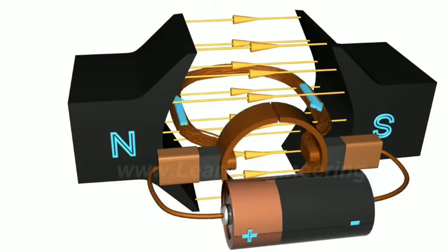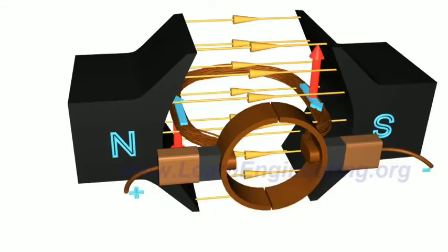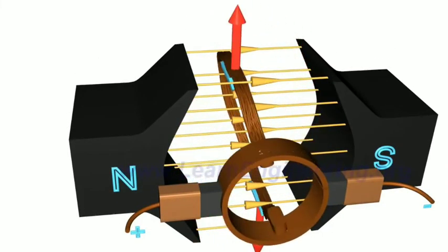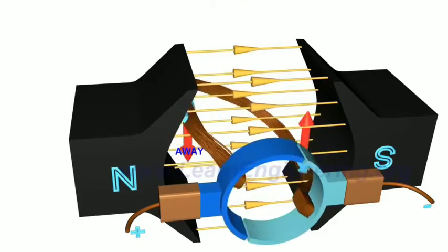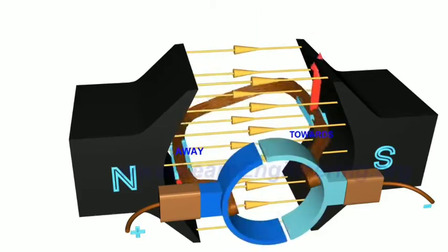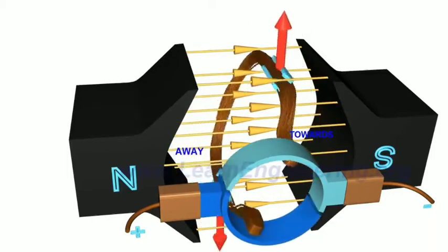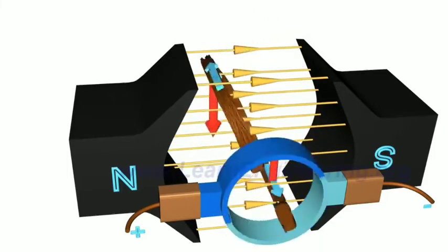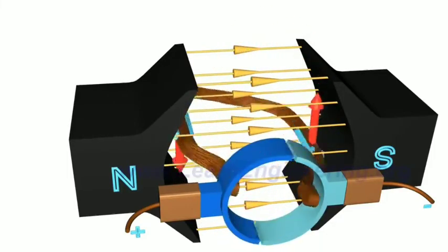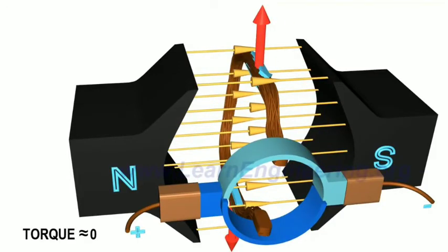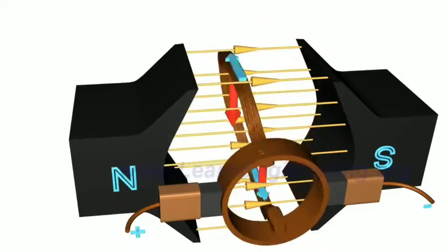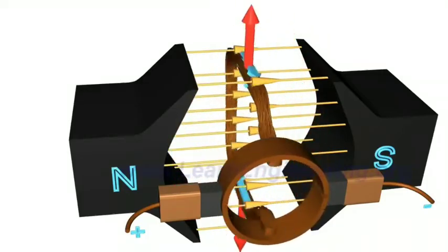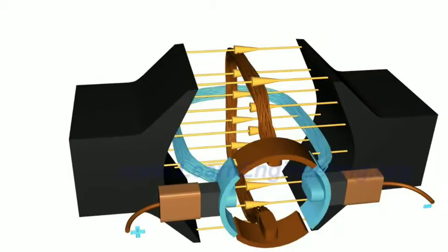Series field DC motors: this motor has large starting torque but is difficult to speed control. Good in applications for starting heavy, non-mobile loads and where speed control is not important, such as for quick opening valves. Shunt field DC motors: this motor has a smaller starting torque, but good speed control characteristics produced by varying field excitation current. Good in applications where speed is to be controlled, such as in conveyor systems.